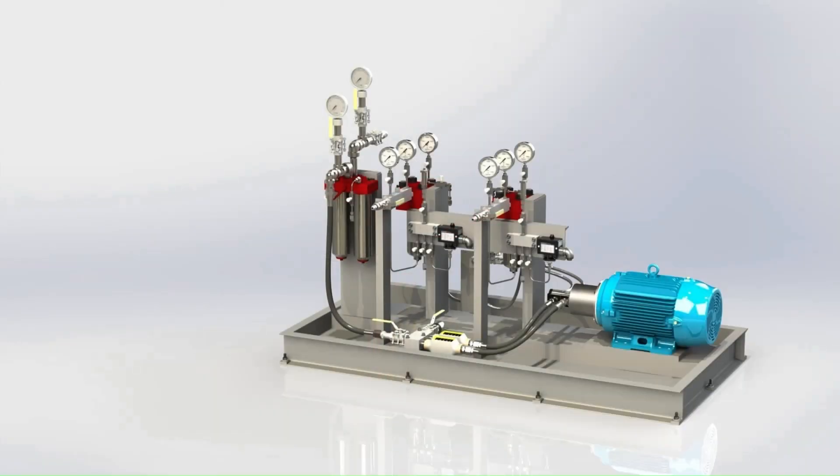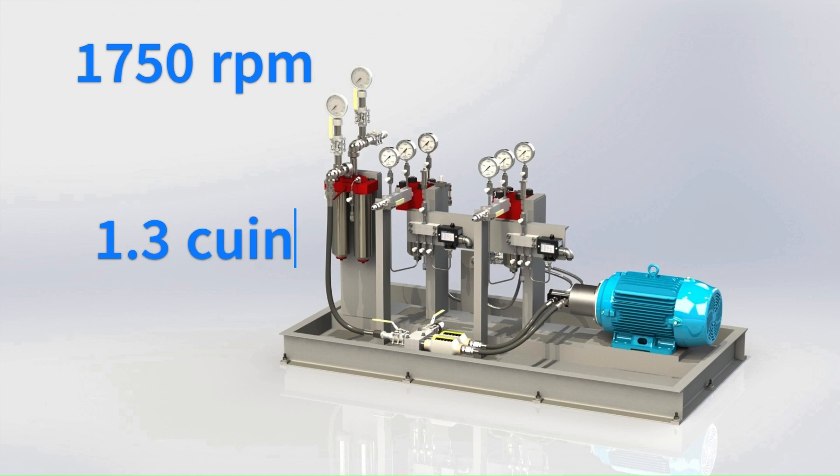Now let's look at an example. Let's assume we will be using a motor that will operate at 1750 RPM and a pump with a displacement of 1.3 cubic inches. We multiply these together to get a volume measured in cubic inches per minute.